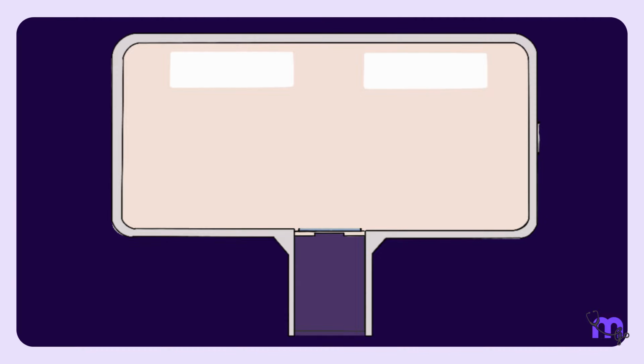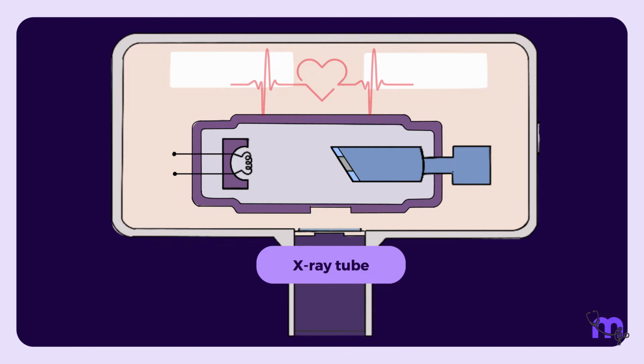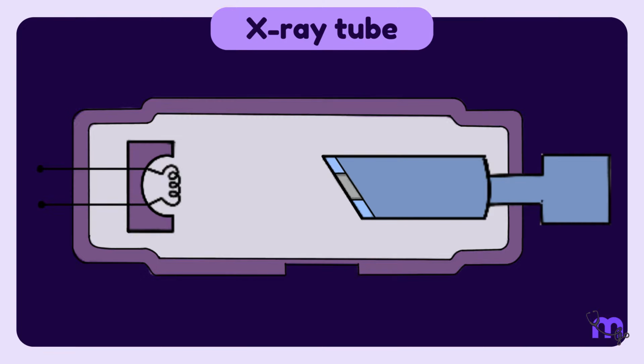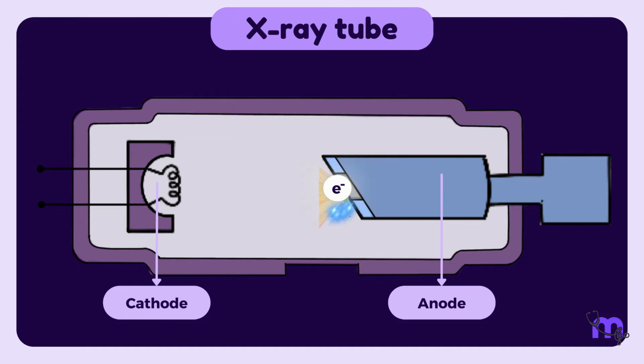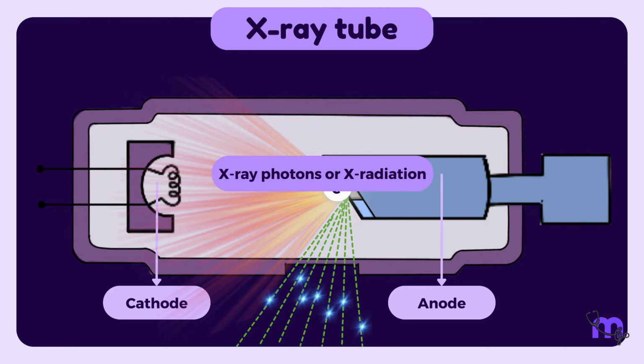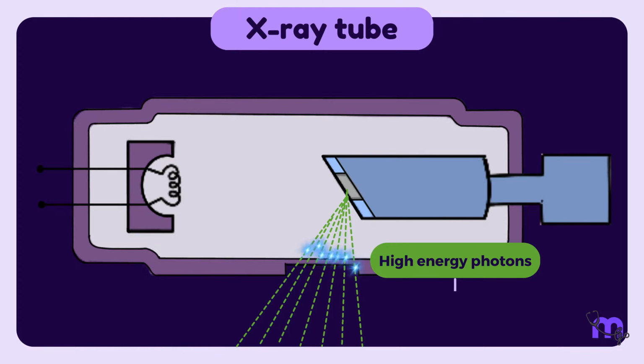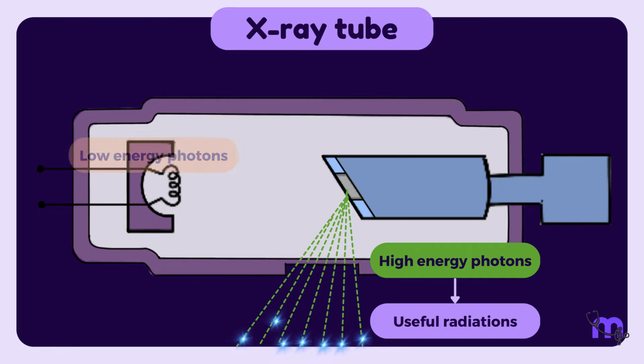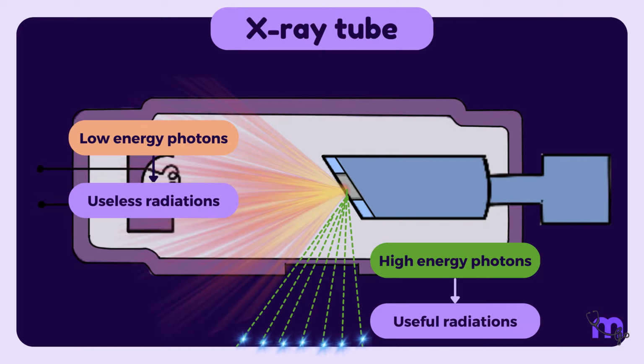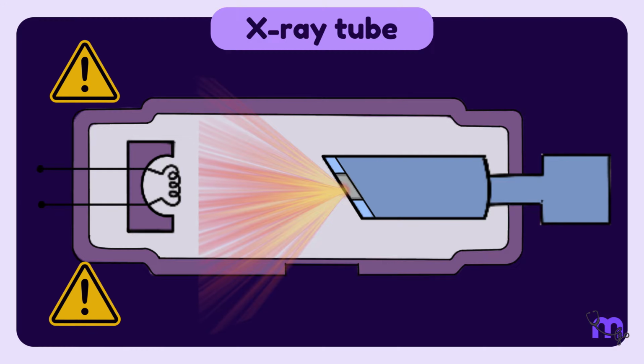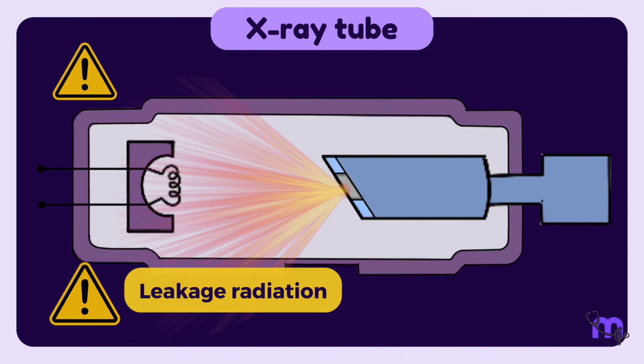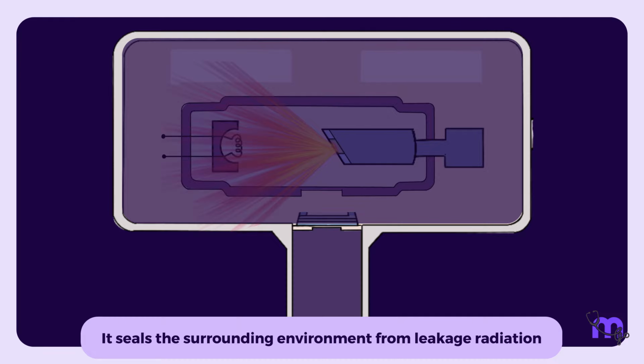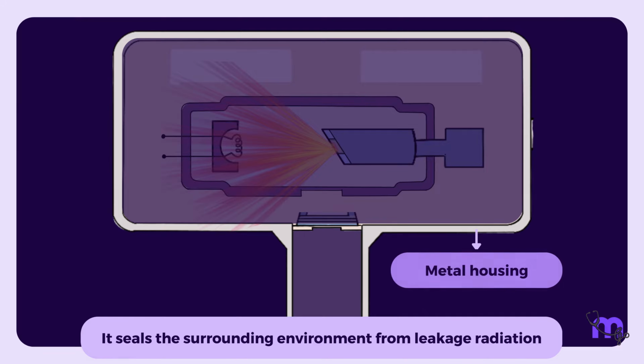At the very center of the X-ray tube head lies the X-ray tube itself, the heart of the machine. Within it, high-speed electrons originating from the cathode hit the target anode to produce X-ray photons, or X radiation. However, not all X-rays created are equal. The high-energy ones contribute to the useful X-ray beam, while the low-energy photons are useless and expose the patient to unnecessary radiation. To protect the surrounding environment from these X-rays or leakage radiation, the X-ray tube is encased in a tightly sealed metal body, aptly named the metal housing.